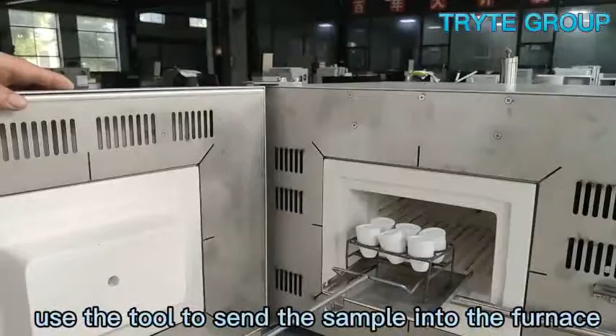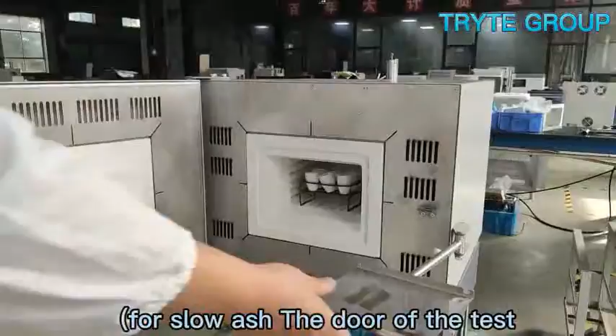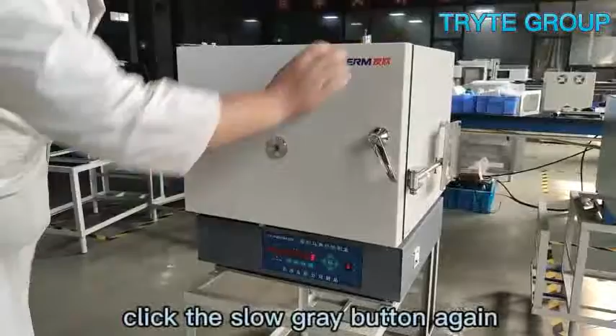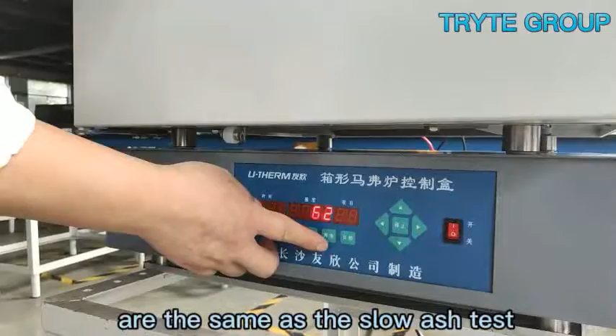Place the tray. Put the prepared sample on the tray. Use the tool to send the sample into the furnace. Remove the tray, and close the furnace door. For slow ash, the door of the test furnace does not need to be closed tightly. Click the slow ash button again. The heating light flashes. The instrument starts to heat, and the experiment begins. The fast ash and volatilization experiments are the same as the slow ash test.